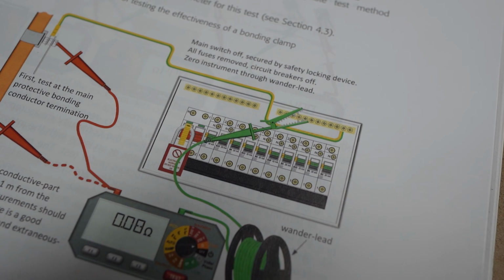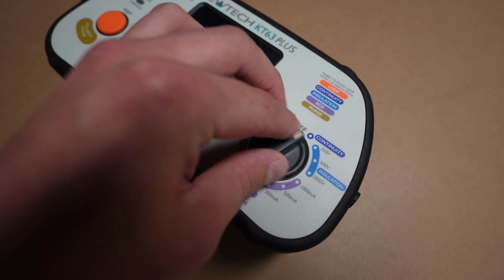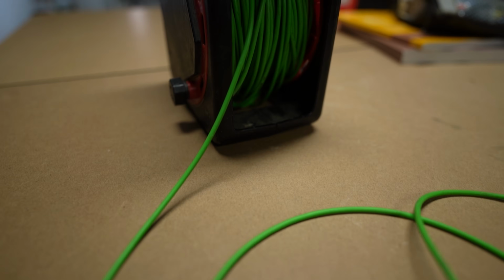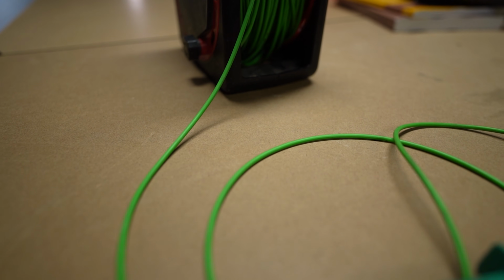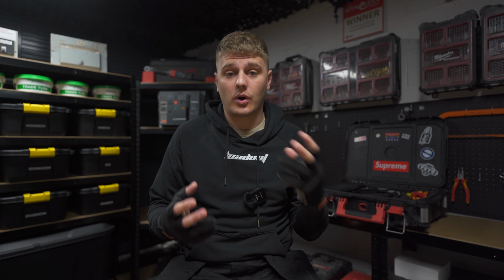Now, before we get into that test, I just want to talk about the science and theory behind the test and bonding itself. So firstly, the test: you're going to be using a low resistance ohmmeter or a multifunction tester configured to this setting. You're essentially taking a long lead from the MET or the origin of the bond to the other end of it to verify continuity, also see if it's within a prescribed value. But to get into the science and theory of bonding, first we need to understand what bonding is, and to understand what bonding is, we might need to understand what earthing is.